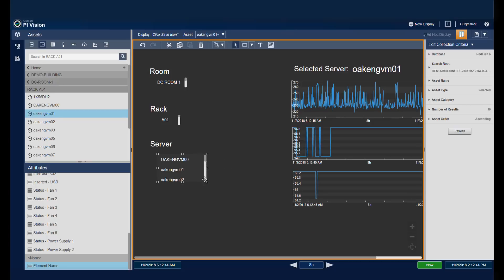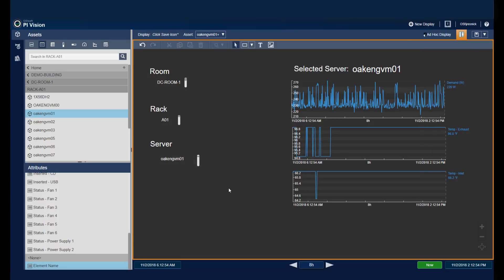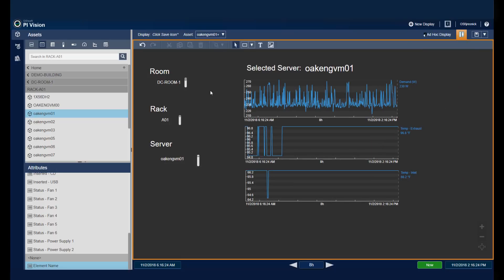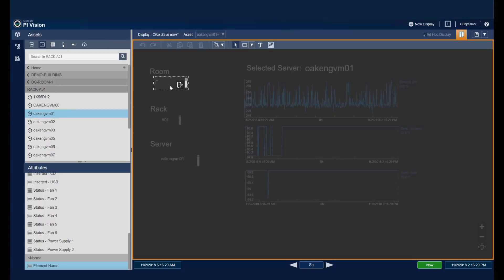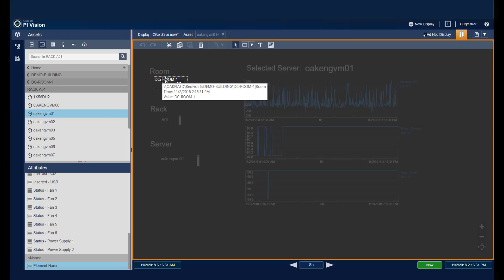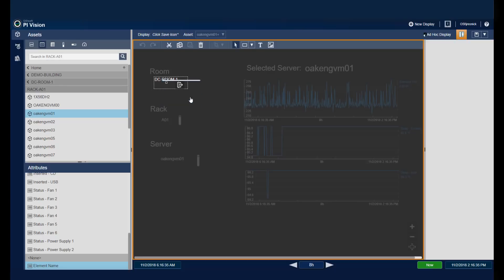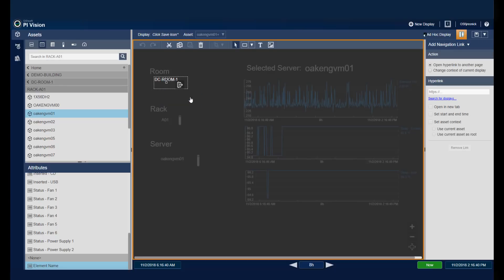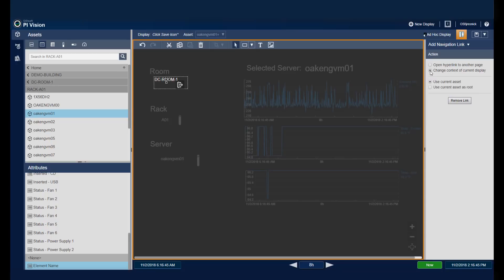So now comes the important part, which helps make this multi-filter work. And that's going to be creating these navigation links. So what I'll need to do is right click and do modify the collection. I need to select my individual attribute. Right click. And do add a navigation link. For this navigation link, we'd like to change the context of the current display. Because that's going to adjust how the other items on this display behave. And we want to use this current asset as the root for the rest of the display. We're going to do the same steps for the other ones as well. And that ensures that the rest of the display adheres to the root that we're selecting as we drill down through these multi-tiered filters.